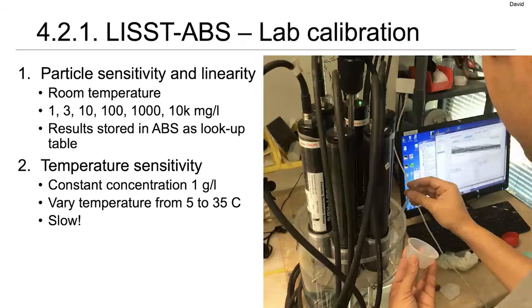I will say that at 1 milligram per liter, the number of particles involved in that, especially the number that are passing through the sensitive range at any given moment, is small. At the low end of the concentration range, the data are inherently noisy just because of the physical characteristics of the measurement. So we typically state that 1 milligram per liter is the low end of the measurement range. Also keep in mind that the particles that we use are the ones that are at the peak of the sensitivity of the instrument. So if your particles are smaller, you would probably not be able to measure down to that 1 milligram per liter range.